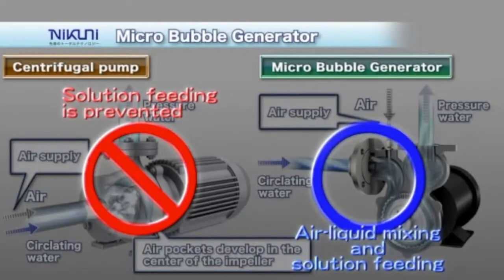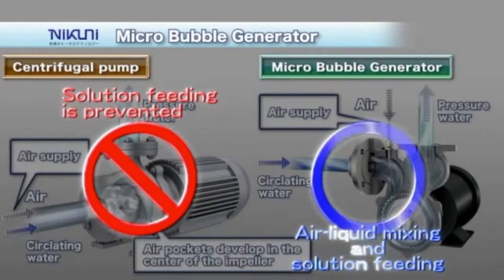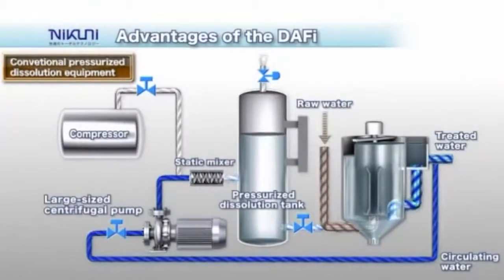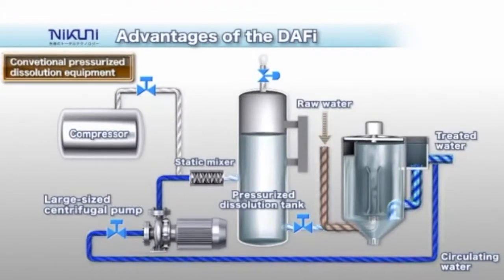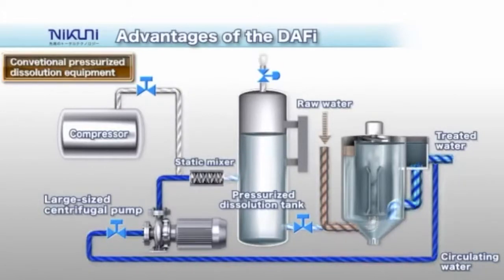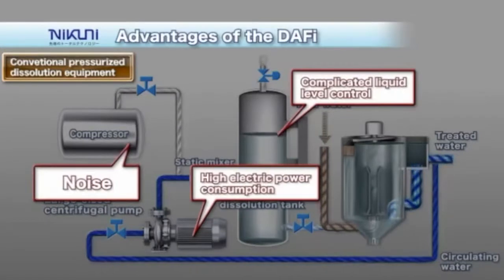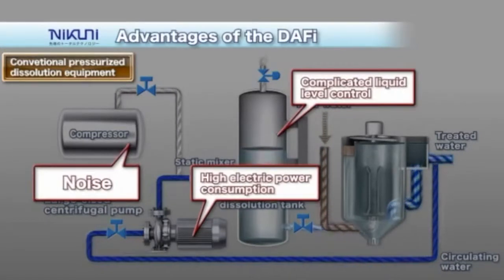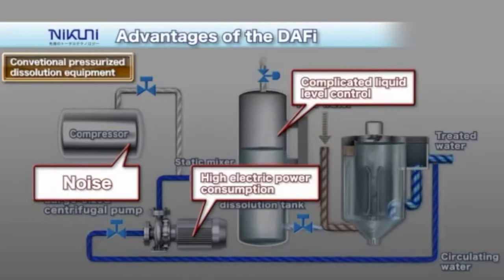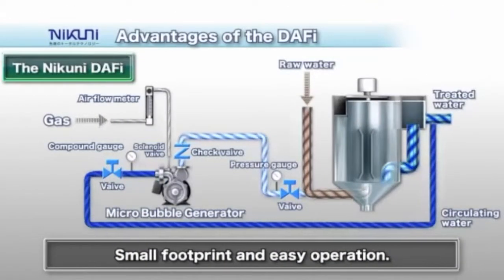Additional advantages of the Nikuni DAFi include a simple and robust design and easy operation. Typical pressurized DAF systems require a large centrifugal pump and a pressurized dissolution tank, along with a noisy air compressor and static mixer. This arrangement uses a large amount of power and makes it difficult to maintain liquid level control in the pressurized dissolution tank.